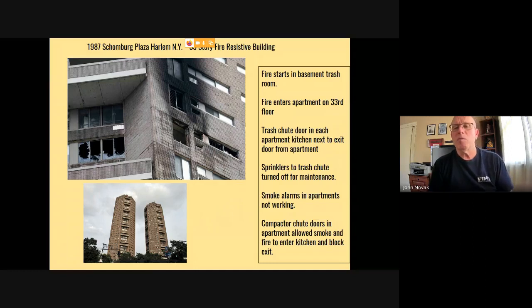The other issue was there were sprinklers in the chute, every so many floors. From what I understand, the sprinkler system was shut down a few days prior for maintenance and was never turned back on over the weekend. The fire started on a Sunday morning. It was reported that smoke alarms in the building weren't working. So the fire was located in the trash chute, in the trash compactor room. Fire raced up the steel chute, even though it was an enclosed chute. It exited into one of the apartments, most likely because the compartmentation was breached in the door. Also, the chute was designed to be operated with a working sprinkler system, so any fire would have been tamped down by the sprinkler system. So fire should never have gotten into the apartment.